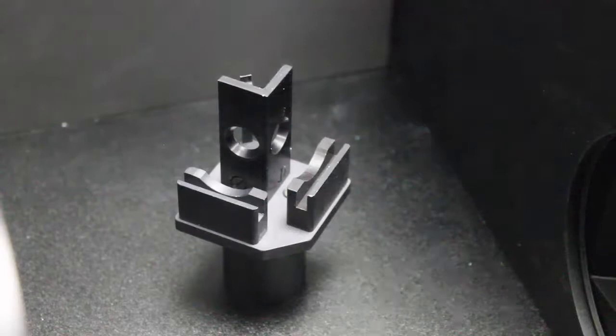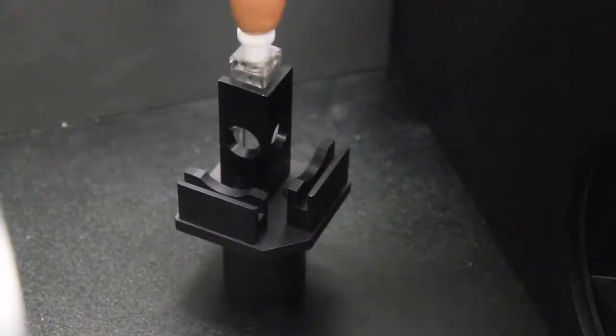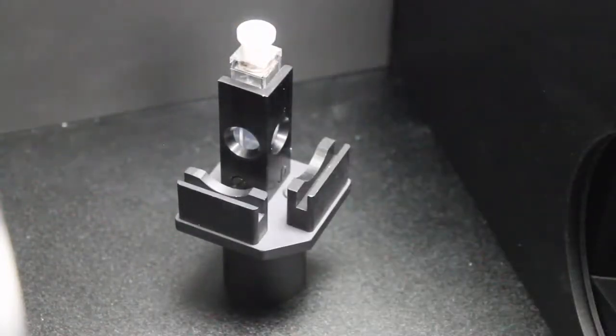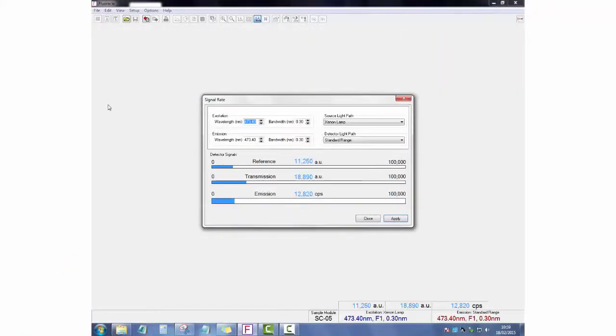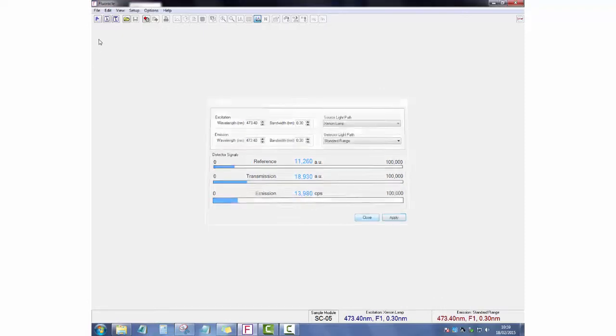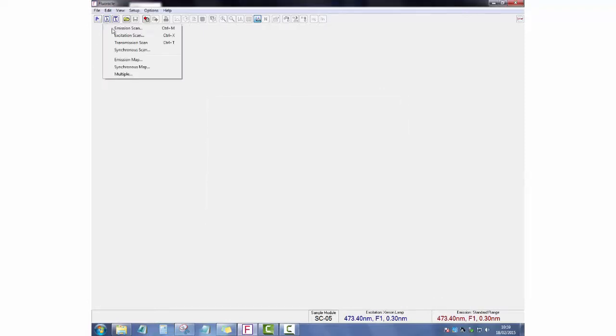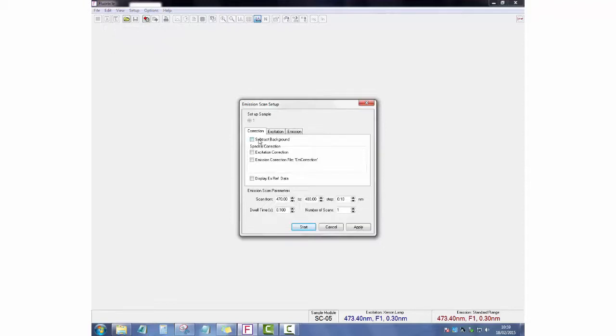In order to calibrate the emission monochromator, we put a scattering solution into the sample cassette, perhaps Ludox from Sigma Aldrich, or even water with a touch of milk. We now set the emission monochromator bandwidth to 0.3 nanometers and set the excitation wavelength to 473.4 nanometers and a bandwidth of around 0.5.